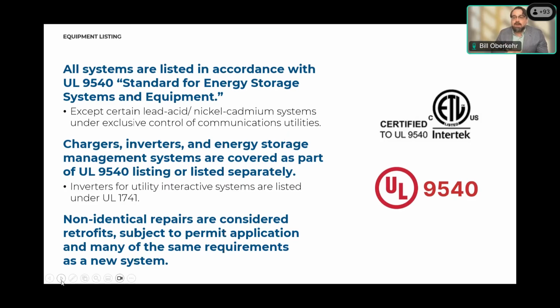This is the UL 9540 equipment listing: Underwriters Laboratories certifying that all the components and subcomponents of the system work safely in harmony together. As Paul mentioned, other UL listings are necessary to get the UL 9540 listing—for instance, the inverter needs UL 1741 listing if the system is grid connected, which almost all are, and the cells need to be UL listed. So there are sub-listings that go into the UL 9540 listing.